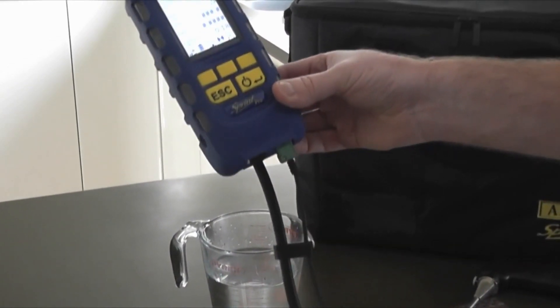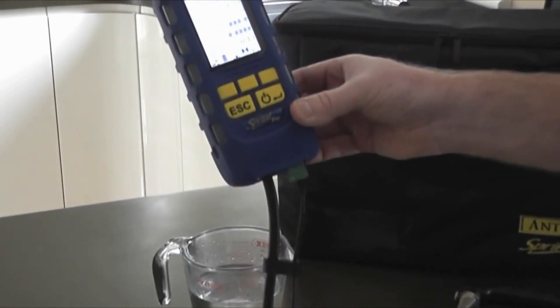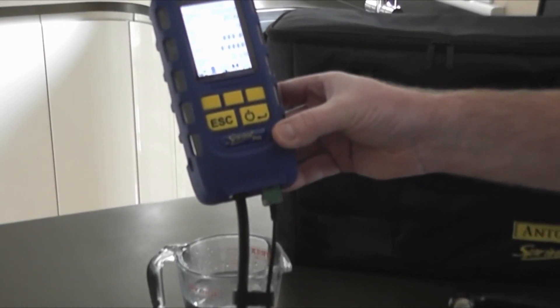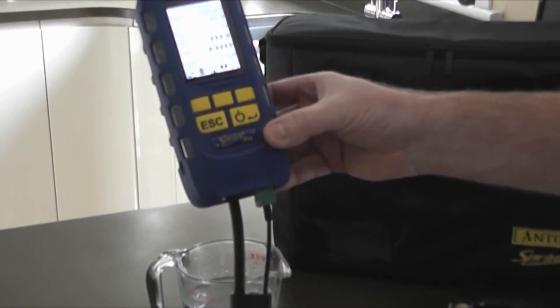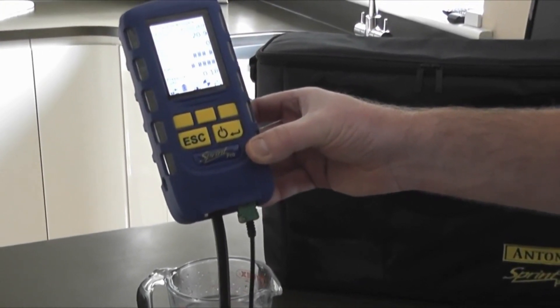So what we expect this to do is to save a lot of unscheduled returns, because a lot of problems when we get analyzers back early is because the filter bowls haven't been emptied, and unfortunately customers get water into their pump, and it causes downtime and frustration.